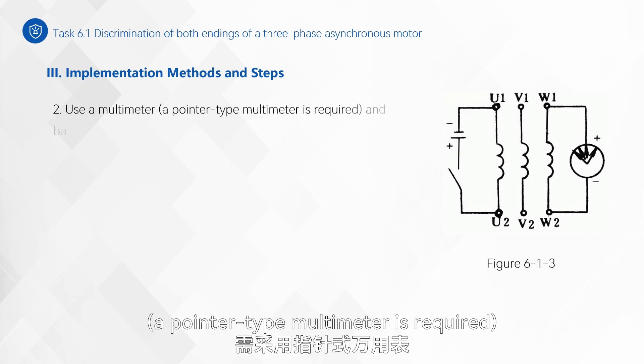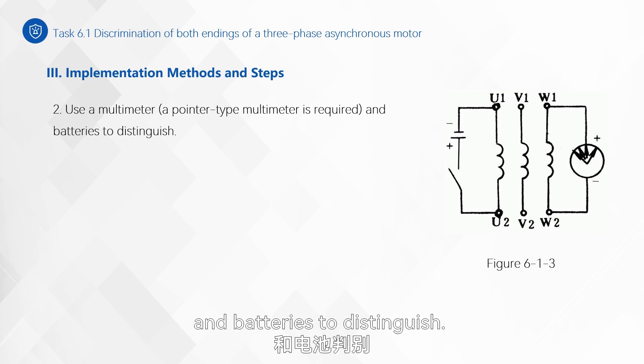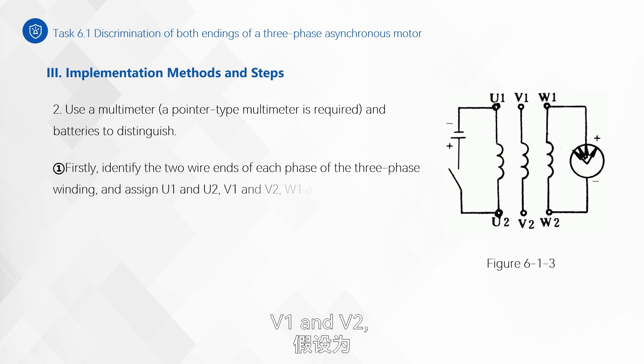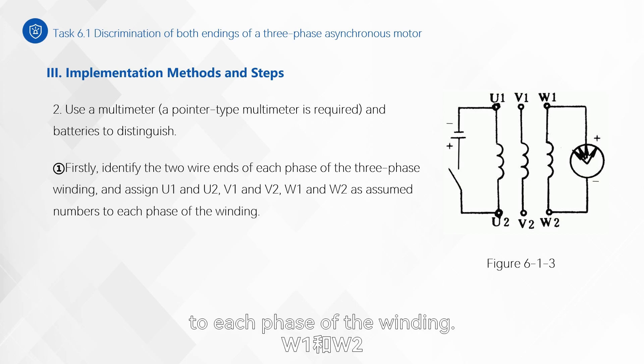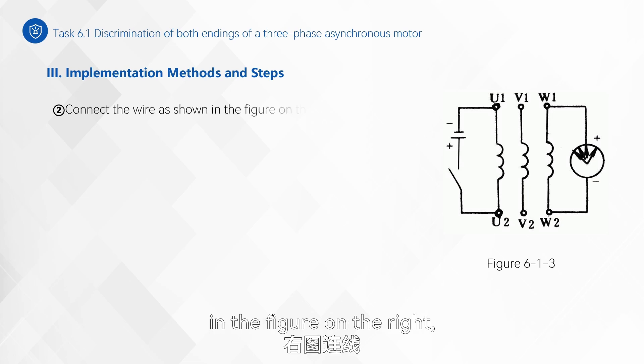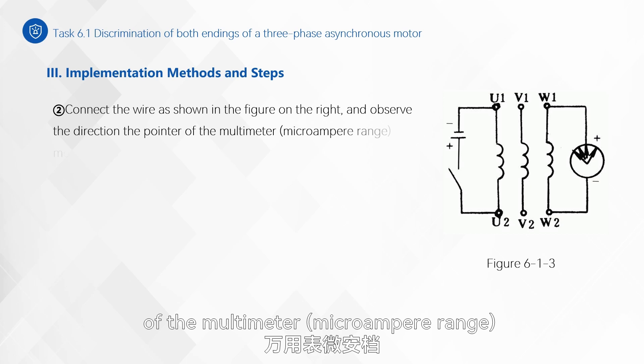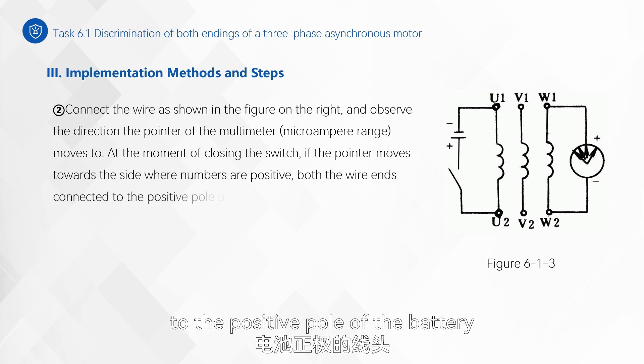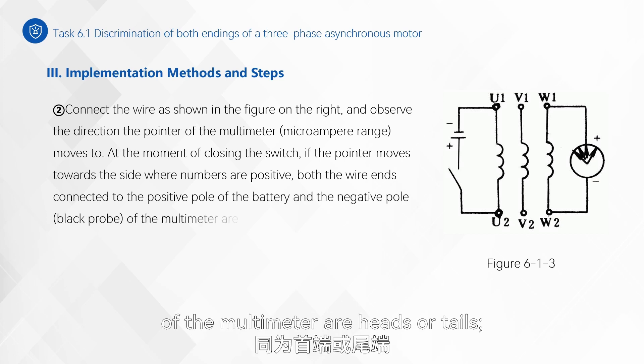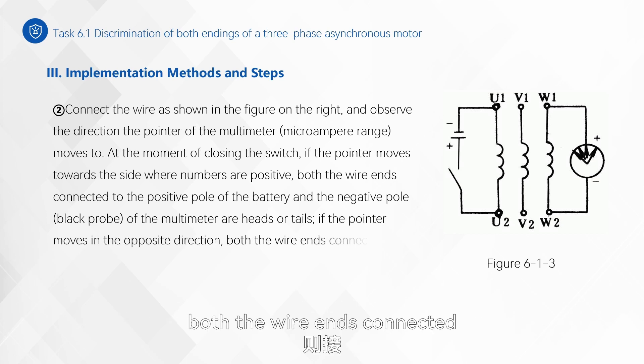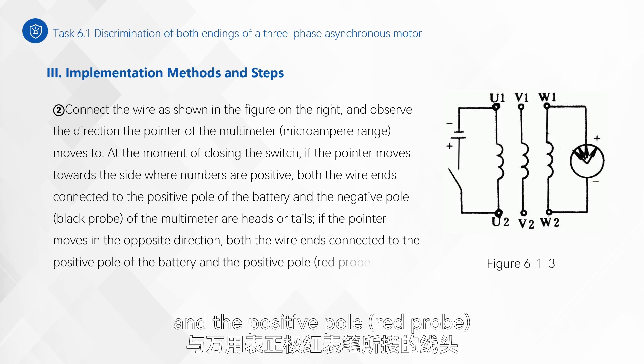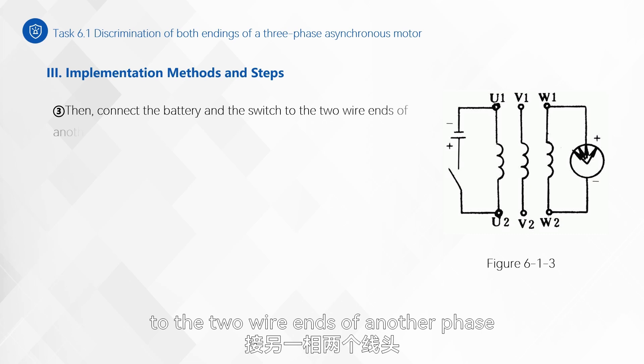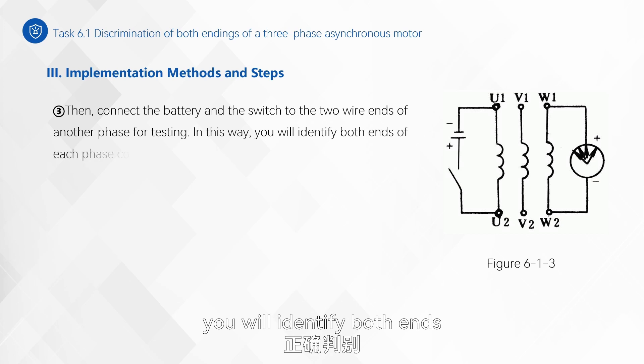Method two: use a multimeter — a pointer-type multimeter is required — and batteries to distinguish. First, identify the two wire ends of each phase of the three-phase winding and assign U1 and U2, V1 and V2, W1 and W2 as assumed numbers. Second, connect the wire as shown in the figure and observe the direction the pointer of the multimeter in the microampere range moves. At the moment of closing the switch, if the pointer moves towards the positive side, both the wire ends connected to the positive pole of the battery and the negative pole (black probe) of the multimeter are heads or tails. Then connect the battery and switch to the two wire ends of another phase for testing. In this way, you will identify both ends of each phase correctly.